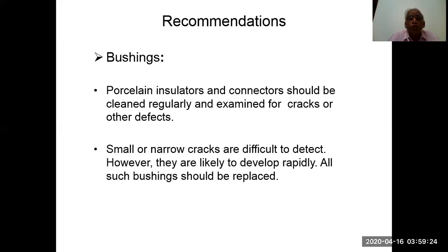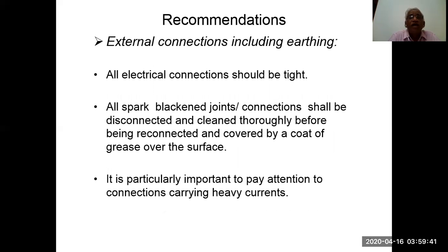Recommendations: bushing. Porcelain insulators and connectors should be cleaned regularly and examined for cracks or other defects. Small or narrow cracks are difficult to detect; however, they are likely to develop rapidly. All such bushings should be replaced on time. External connections, including earthing: all electrical connections should be tight. All spark-blackened joints and connections shall be disconnected and cleaned thoroughly before being reconnected and covered by a coat of grease over the surface. It is particularly important to pay attention to the connections carrying heavy currents.